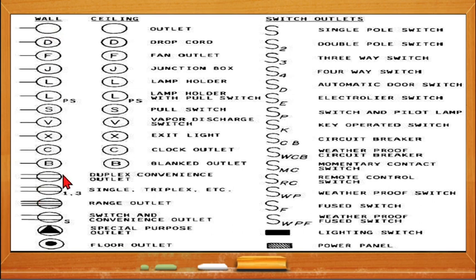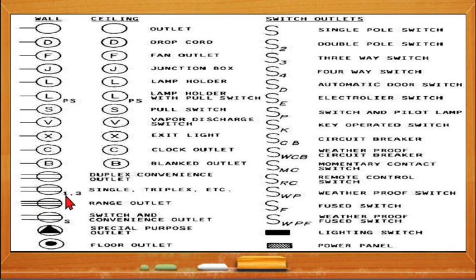We have the wall-mounted symbols, meaning our devices will be mounted on the wall. We have also the ceiling symbols, meaning the devices will be installed in the ceiling — such as junction boxes and lamp holders. For outlets, the duplex convenience outlet symbol is for a two-gang outlet. If you put a '1' beside the symbol, that outlet is single-gang; if you put '3', it's three-gang. Then you have the range outlet with three lines, the outlet with switch for special-purpose or heavy appliances and air-cons, and the floor outlet installed in the floor.